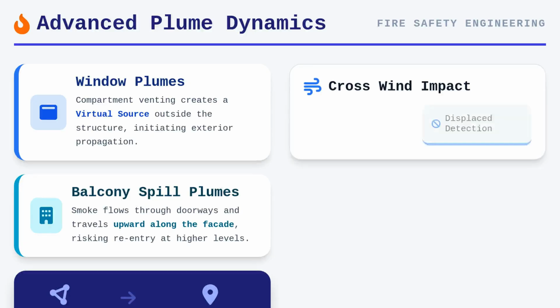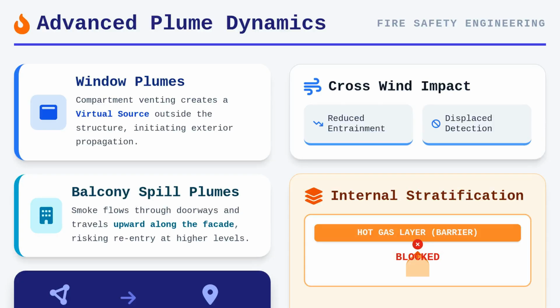Furthermore, we must address external environmental factors such as crosswinds or internal stratification. A crosswind can lean the plume, reducing the effectiveness of air entrainment and pushing the hot gases away from the intended detection zone. Stratification, where a layer of hot gas already exists beneath the ceiling, acts as a barrier that limits the buoyant rise of the plume, a condition that frequently leads to late detection or non-actuation if the design does not account for the ceiling jet's inability to penetrate the layer.